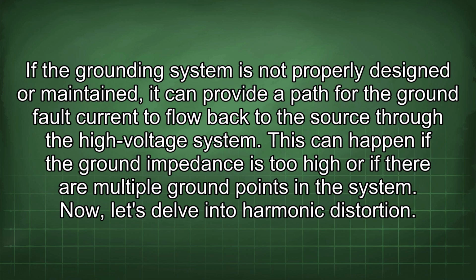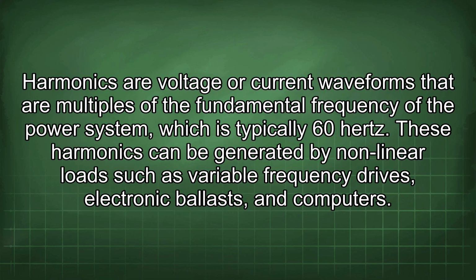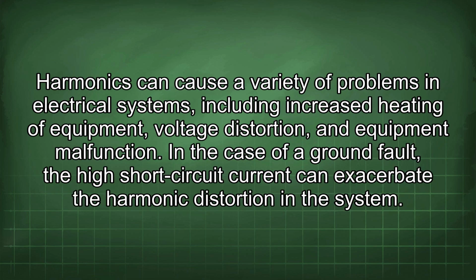Now let's delve into harmonic distortion. Harmonics are voltage or current waveforms that are multiples of the fundamental frequency of the power system, which is typically 60 Hz. These harmonics can be generated by nonlinear loads such as variable frequency drives, electronic ballasts, and computers. Harmonics can cause a variety of problems in electrical systems, including increased heating of equipment, voltage distortion, and equipment malfunction.